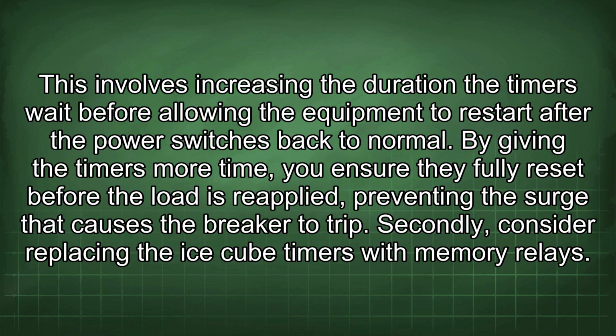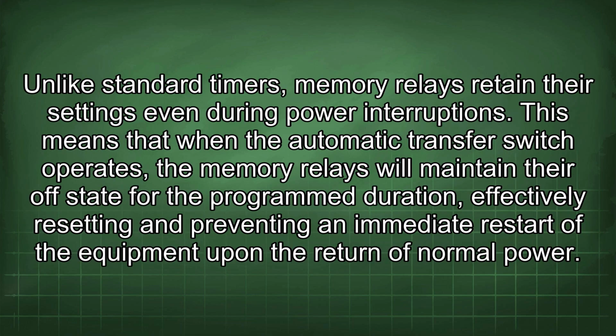Secondly, consider replacing the ice cube timers with memory relays. Unlike standard timers, memory relays retain their settings even during power interruptions. This means that when the automatic transfer switch operates, the memory relays will maintain their off state for the program duration, effectively resetting and preventing an immediate restart of the equipment upon the return of normal power.